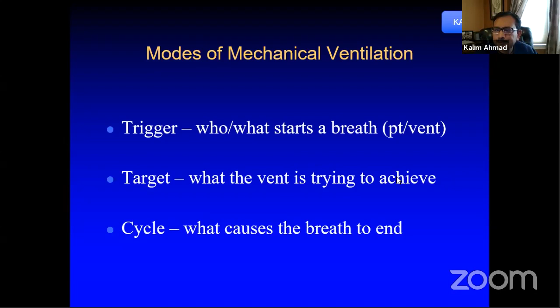And the cycle: when is the machine going to know how to end the breath? Because you told the machine, let's start delivering 10 breaths per minute. But how is the machine going to know when to stop giving air in, how to stop the inspiration, and how the expiration is going to start? Because we know that breathing has two components, breathing in and breathing out, inspiration and expiration. So cycle is the term we use for the mechanical ventilator for how the transition happens from inspiration to expiration. We'll talk in detail in future. Next.